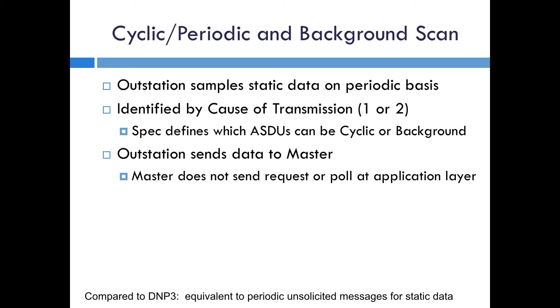Another basic function is the ability for the outstation to have either cyclic, periodic, or background scan. This is a way for the outstation to send sample data to the master on a periodic basis — really for static data which needs to be sent over. So even if the data has not changed, it's still sent with a new sample and could include a time tag. The outstation tells the master the cause of transmission: one is for cyclic, two is for background.